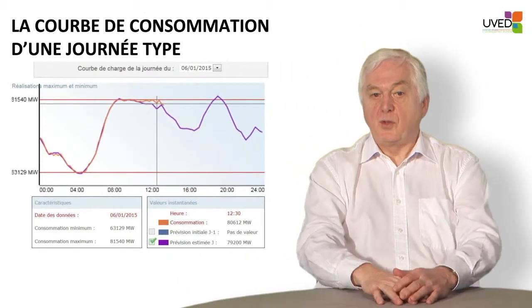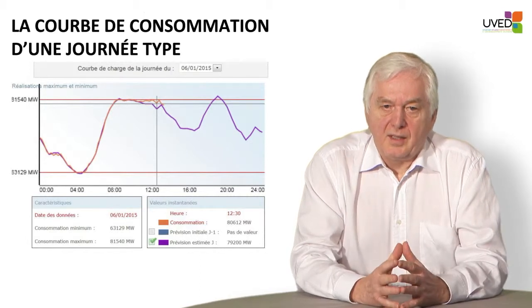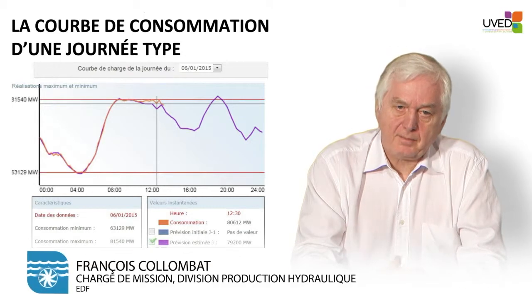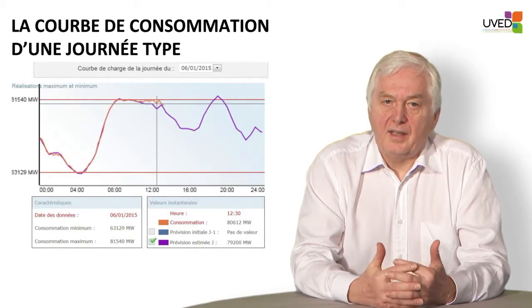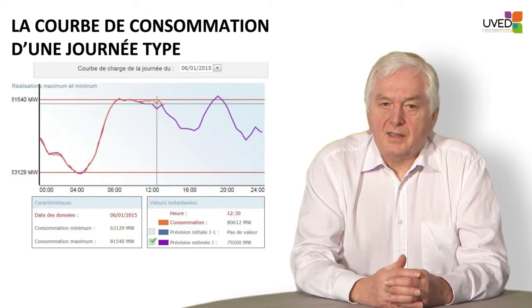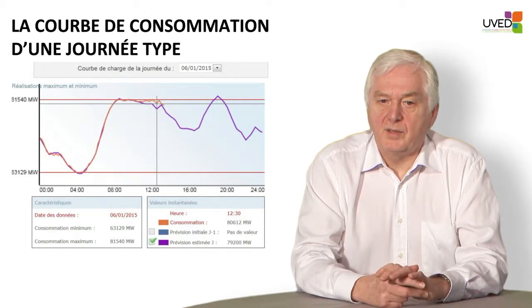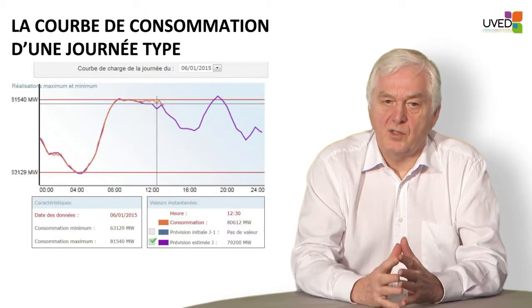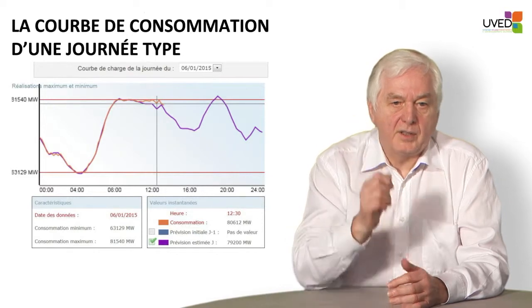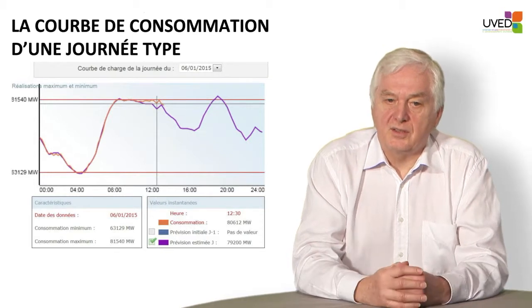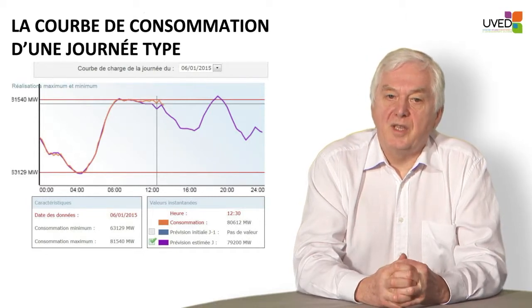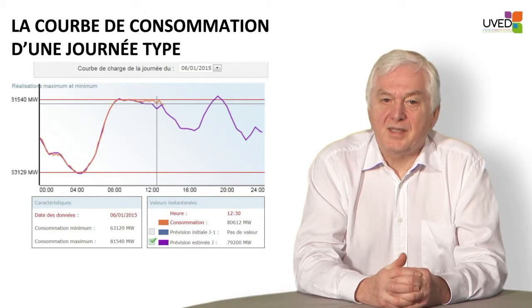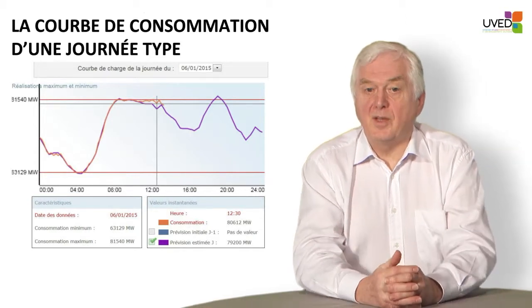Let us now look at the consumption curve during a given day, for instance the 6th of January 2015. The curve is a real-time curve you can look up on the RTE website, updated every 15 minutes. In purple we see the forecast made the previous day. On January 5th, it was estimated that at 4 o'clock in the morning minimum consumption would be approximately 63,000 megawatts, and at 7 o'clock p.m. maximum consumption would be 81,000 megawatts. Between 5 and 7 o'clock in the morning, consumption moves from 65,000 to 80,000 megawatts.